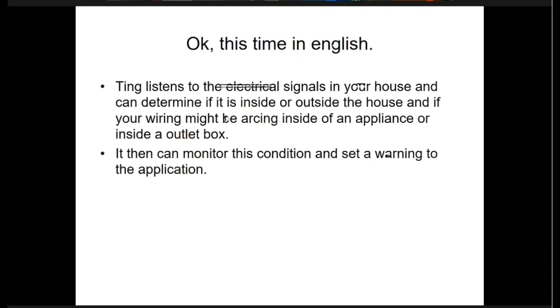Now in English: it's listening to the electrical signals in your house and can determine if a disturbance is inside or outside the house, and if your wiring might be arcing inside an appliance or inside an outlet box. It can then monitor this condition and set a warning to the application.